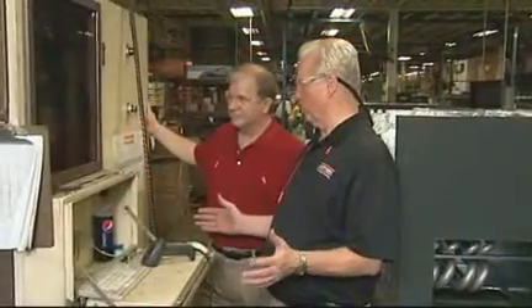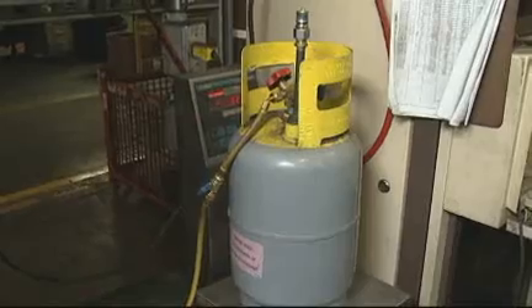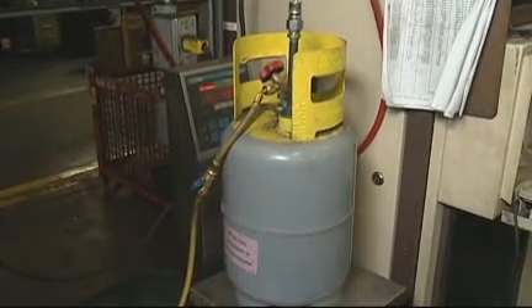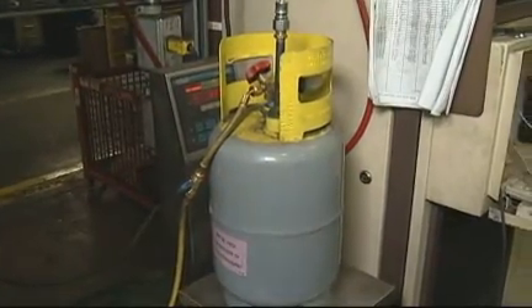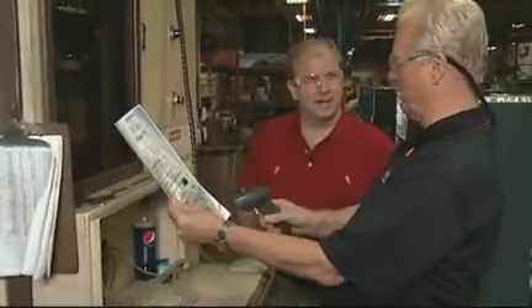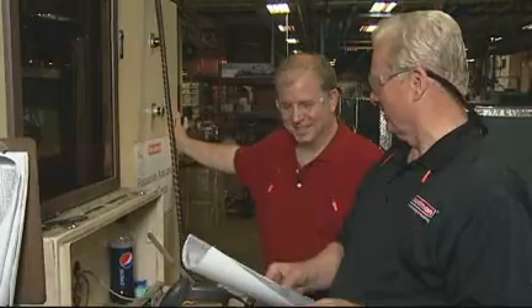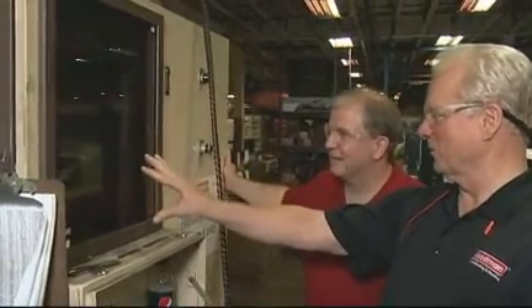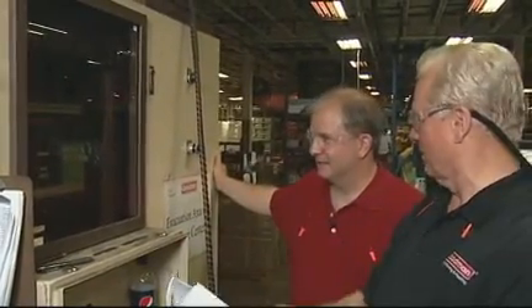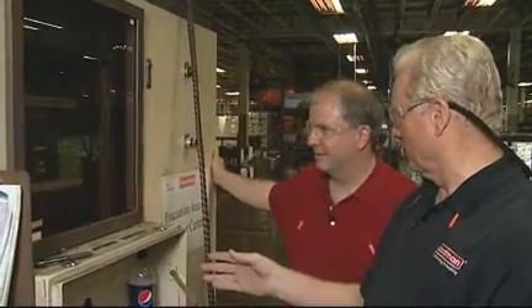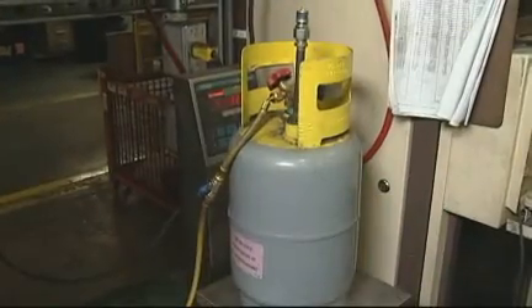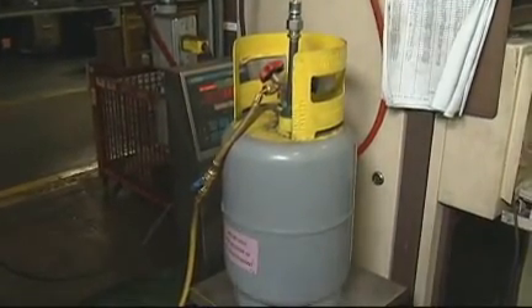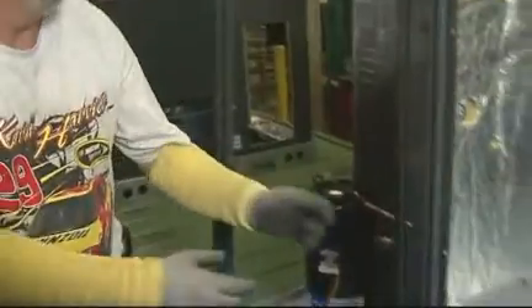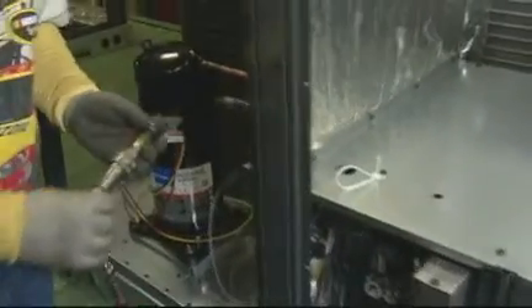This is the charge board station. This is where the unit is charged with the precise amount of refrigerant. The way the operator does that, take the serial plate, scan the serial plate. No human intervention, no typing in a serial number. Right. The computer automatically reads what the serial number and model number it is. It's automatically programmed to put the exact number of ounces of refrigerant that goes in that particular model. For quality of the product, it's got to be right.